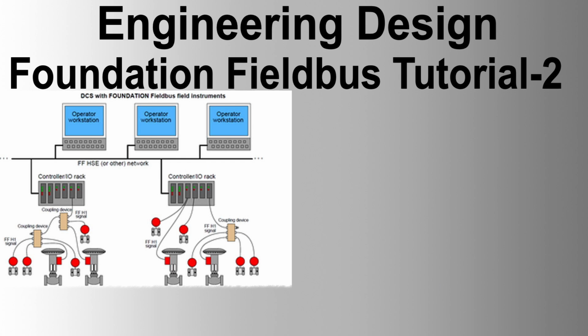IP, Internet Protocol, is used to transfer data to a desired station IP address. Foundation Fieldbus utilizes IP version 4 today and will switch to the much more powerful IPv6 in the near future. TCP, Transmission Control Protocol, provides connection-oriented transport services that can be used for client-server communication. UDP, User Datagram Protocol, transfers an amount of data to a desired application and can be used for source-sink communication. Publisher-subscriber communication can use either TCP or UDP.